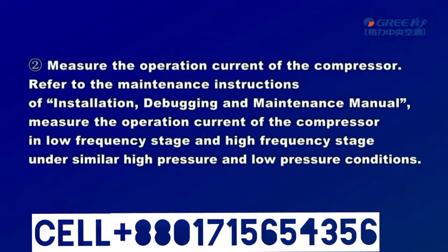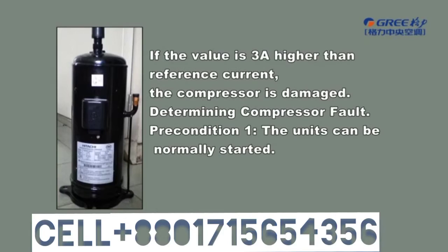2. Measure the operation current of the compressor. Refer to the maintenance instructions of the installation, debugging, and maintenance manual. Measure the operation current of the compressor in low frequency stage and high frequency stage under similar high pressure and low pressure conditions. If the value is 3 amperes higher than the reference current, the compressor is damaged.